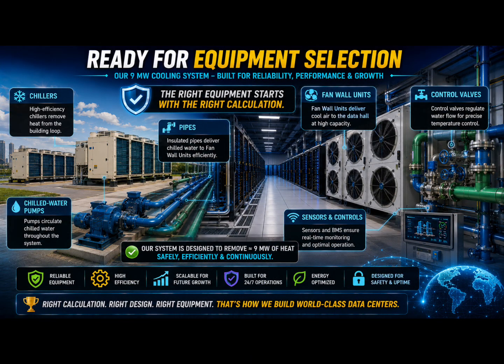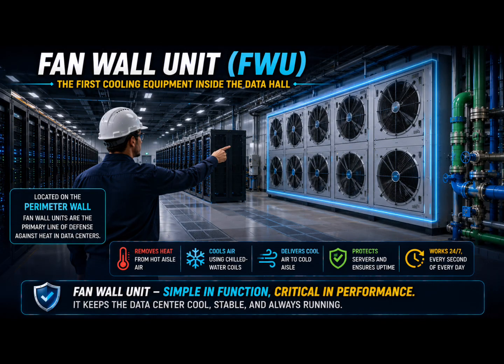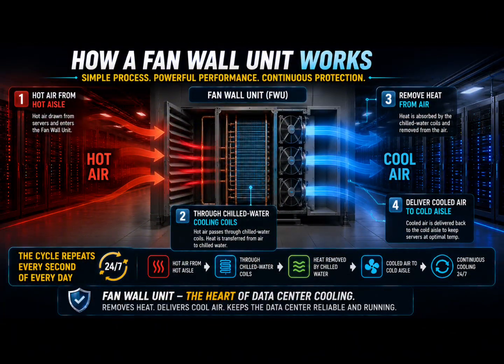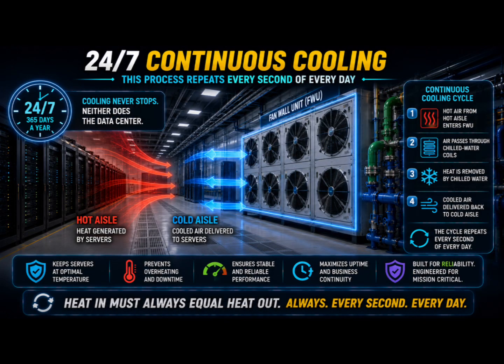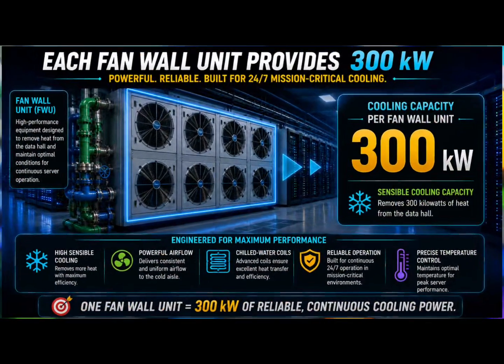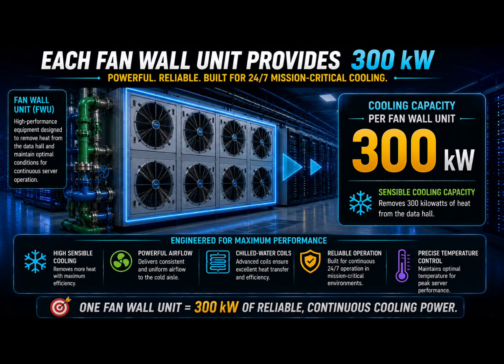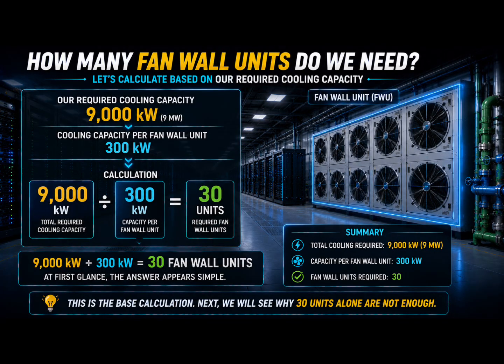The first equipment inside the data hall is the fan wall unit. Its job is straightforward. Draw hot air from the hot aisle, pass that air through chilled water cooling coils, remove the heat, and deliver cooled air back to the cold aisle. This process repeats every second of every day. For our design, each fan wall unit provides 300 kilowatts of sensible cooling. Now, let's determine how many units we need. Our required cooling capacity is 9,000 kilowatts. 9,000 divided by 300 equals 30. At first glance, the answer appears simple. Install 30 fan wall units.